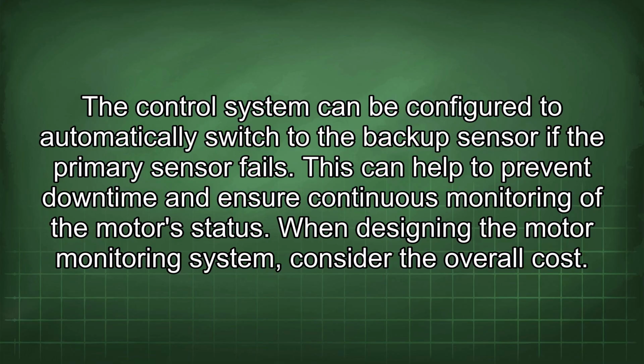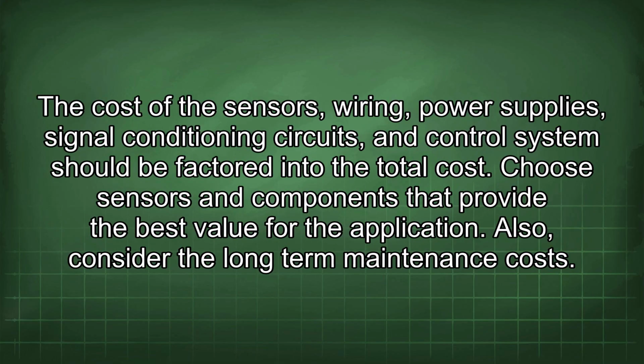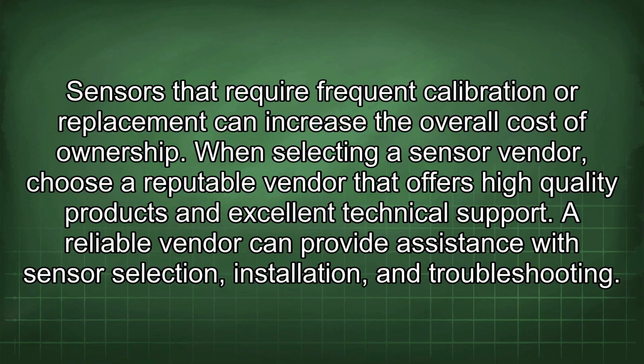When designing the motor monitoring system, consider the overall cost. The cost of the sensors, wiring, power supplies, signal conditioning circuits, and control system should be factored into the total cost. Choose sensors and components that provide the best value for the application. Also, consider the long-term maintenance costs. Sensors that require frequent calibration or replacement can increase the overall cost of ownership.